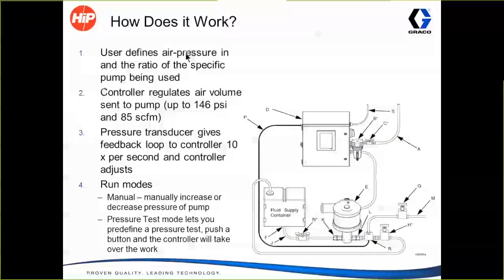All right, hello everyone. So to start with this system, remember this is an automation control box that allows you to do 2 things. One is control a pneumatic pump. It can also be installed on a pre-existing manual test bench and allow you to run that system automatically. So basically this box would replace the manual controls that are already installed on that system.